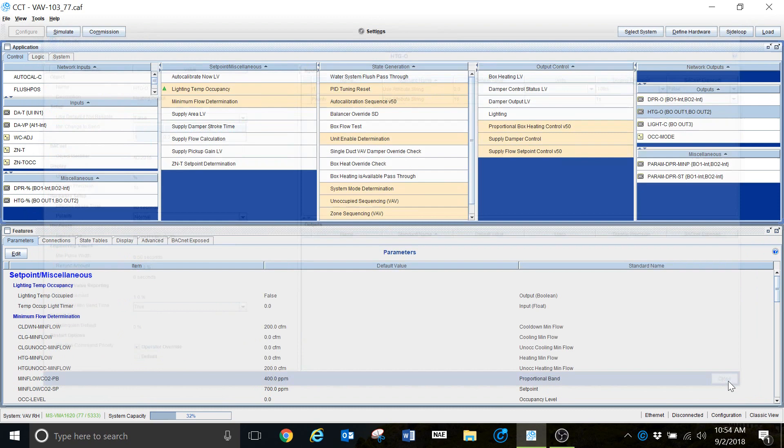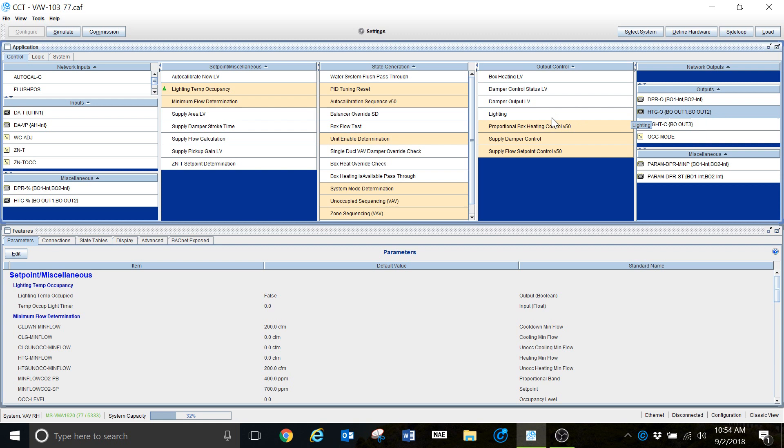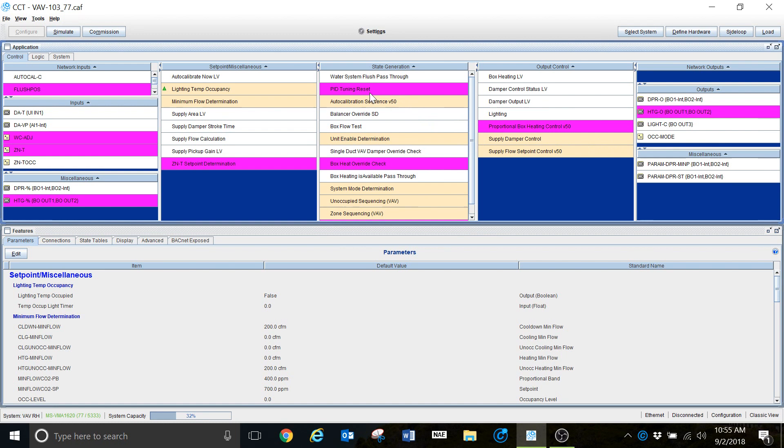What I want to know is what is inside this programming that is controlling this heating output. Right-click, go down to Show Involvement. When I click that, it is going to highlight every one of the logic blocks that influence this particular output. You can see here: Proportional Heating Control. This is the first block we've come to that's going to influence the way that this is controlled.